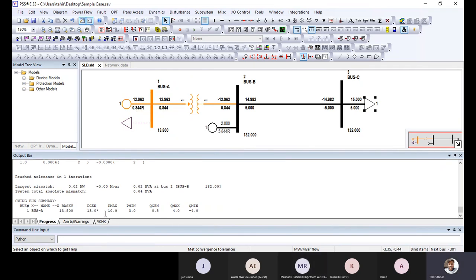No, it is not correct that we need to supply this megawatt in the swing. Basically, in practice, in a real network, there is no concept of a swing bus. A swing bus is only theoretical, in a calculation. Basically, the swing bus gives you a hint of how balanced my system is. Now, you can see here the asterisk is here.